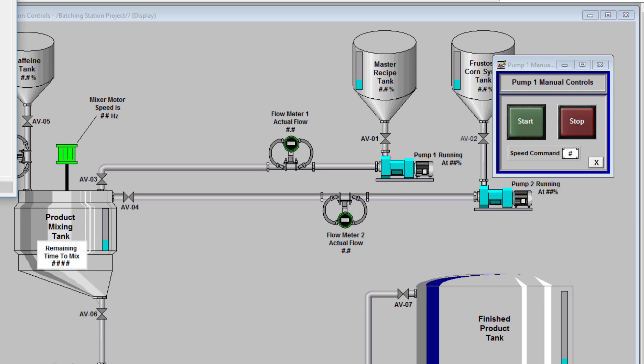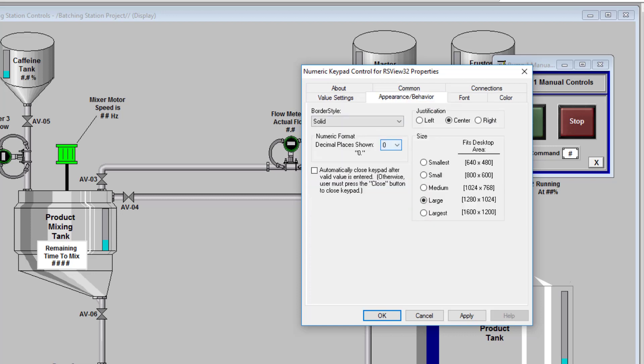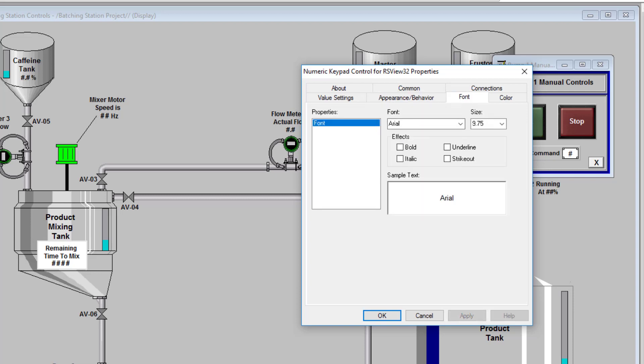You don't have to use ActiveX — you can do a general display if you want. This pop-up screen here: we'll call the title 'Pump 1 Manual Speed.' As far as units, you can put units if you want; I'm just going to leave it. Zero to 100 is generally what you want. For appearance, you can add a decimal — that's where you select the decimal point. In our instance we're not going to have a decimal, since we're just running 10%, 20%, 30%, 40%, etc.